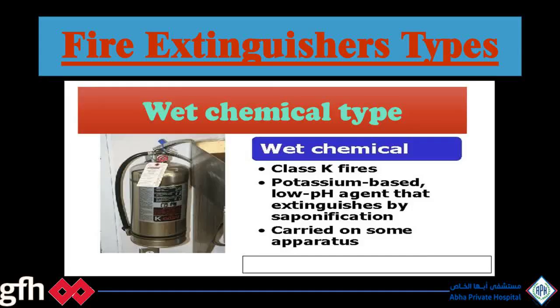Wet chemicals type fire extinguisher. A wet chemical fire extinguisher is specifically designed to combat fires involving cooking oils and fats. These types of fires are classified as Class K. Wet chemical extinguishers contain a solution of potassium acetate, potassium carbonate, or potassium citrate. When discharged, this solution reacts with the burning oil or fat in a process called saponification, creating a thick, soapy foam. The chemical solution cools the burning oil, which helps to extinguish the fire. The foam creates a barrier on the surface of the oil, cutting off the oxygen supply and preventing reignition.